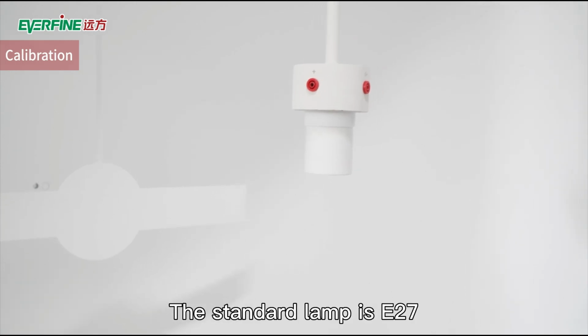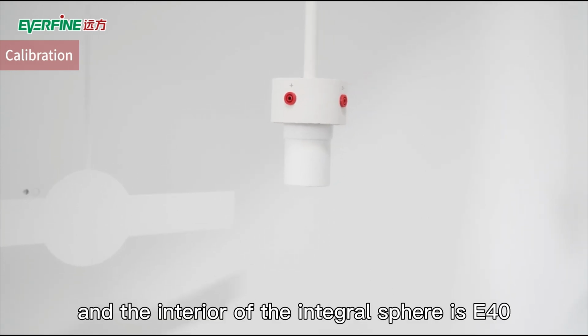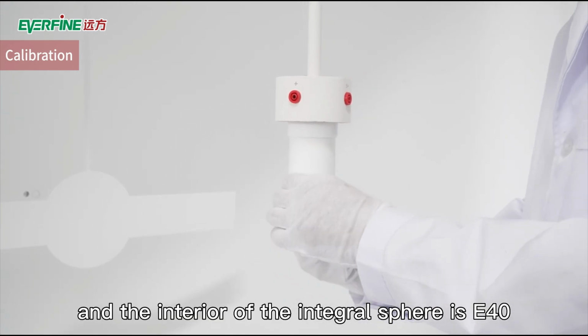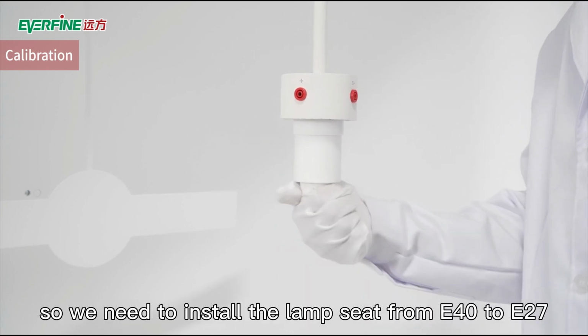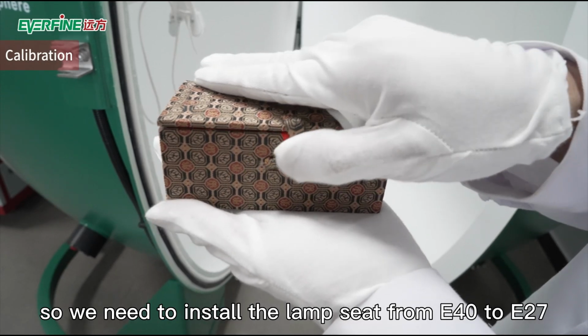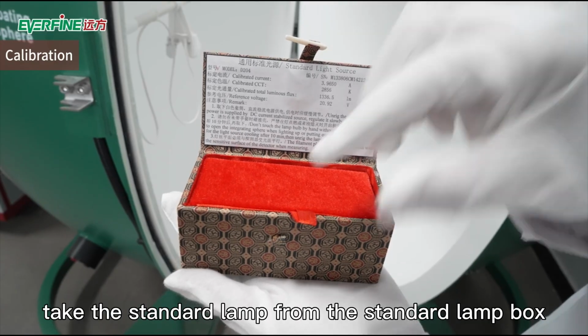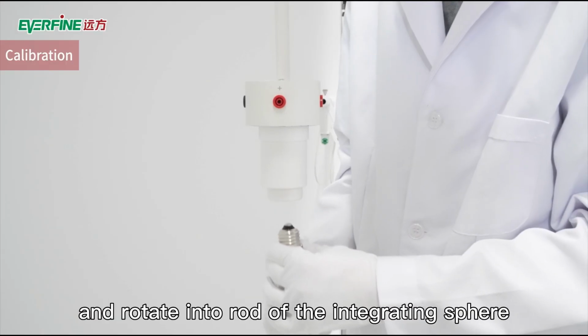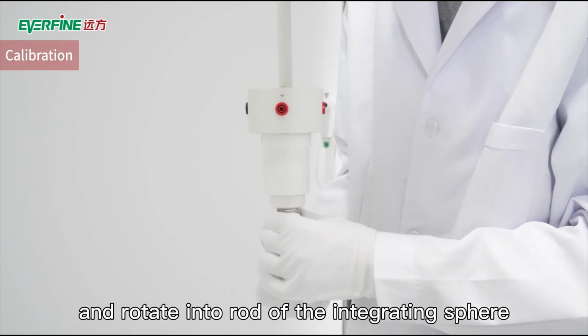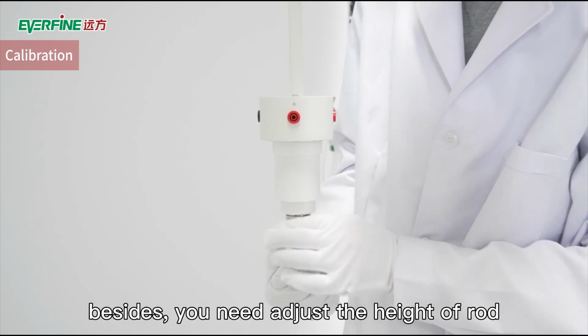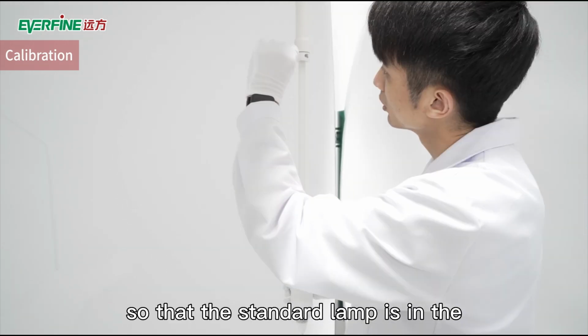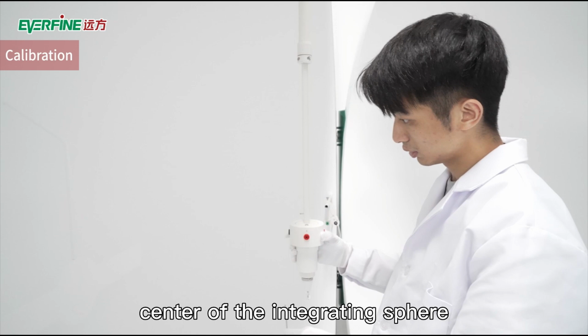The standard lamp is E27, and the interior of the integrating sphere is E40. So we need to install the lamp seat from E40 to E27. Take the standard lamp from the standard lamp box, and rotate it into the rod of the integrating sphere. Besides, you need to adjust the height of the rod, so that the standard lamp is in the center of the integrating sphere.